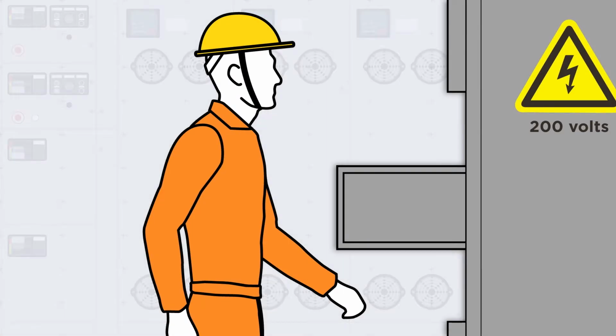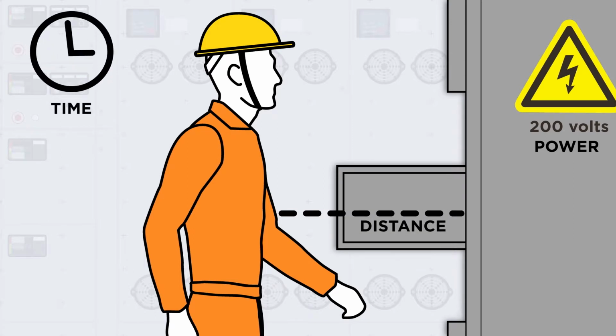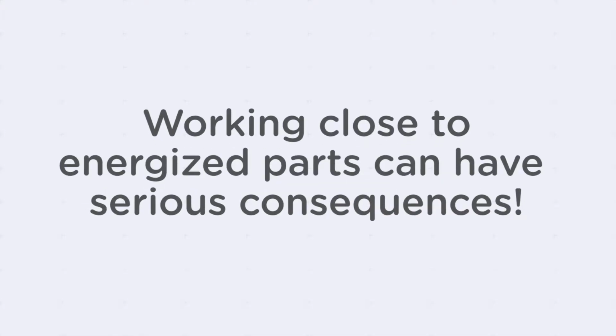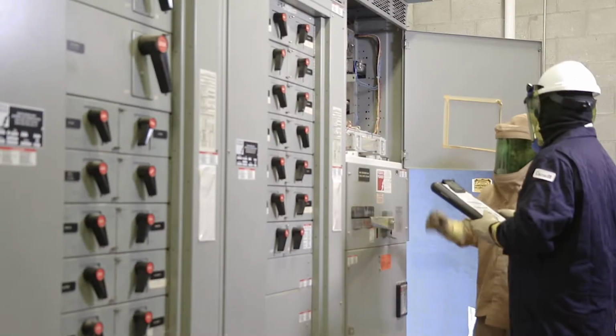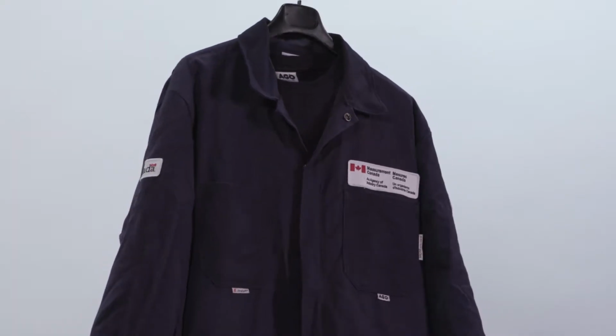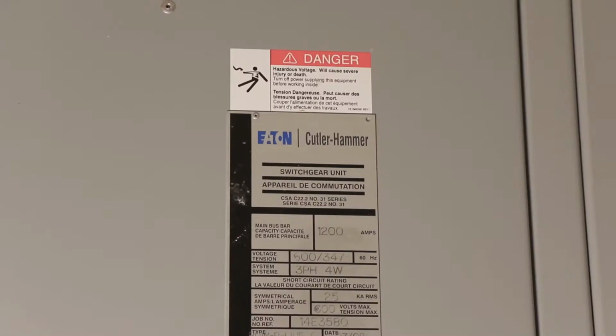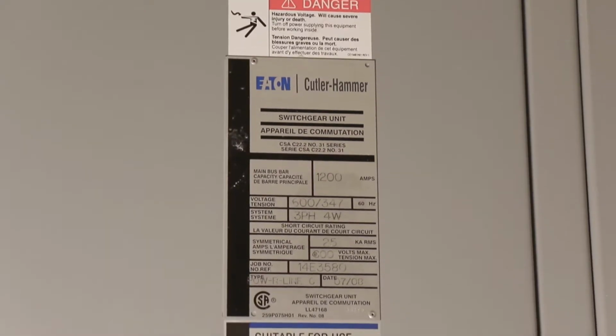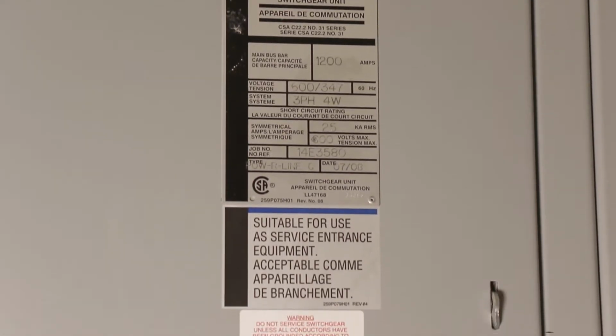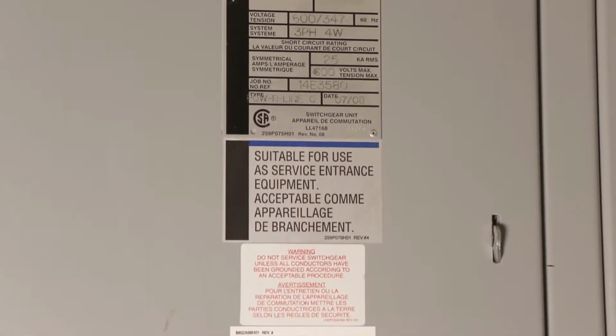The 3 main risk factors associated with arc blasts are power, or the amount of energy at the arc, the distance of the worker to the arc, and time, or the duration of the worker's exposure to the arc. Contact with live circuits or working close enough to the energized part to generate an arc can have serious consequences. A minimum of Category 2 arc flash clothing is required when inspecting all energized electrical installations. Follow all posted incident energy labels or consult with on-site personnel to determine if Category 3 AF PPE is required.